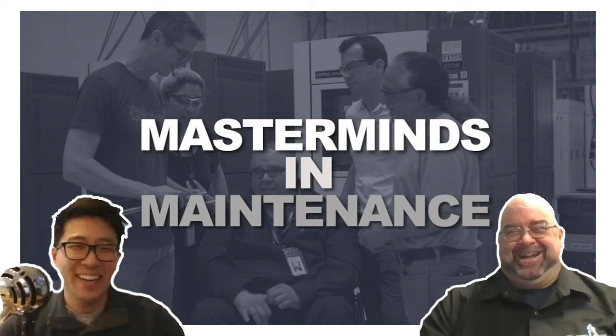Vibration in the wind industry is determined to be about 56% accurate. Electrical signature right now has been determined to be greater than 90%. Wow. Now, what is the primary difference and why is that? Electrical signature is a system analysis. There are things we will detect much later than vibration or ultrasound and other things, but we will see them. And there are things we'll see that they will never see, but we're going to see it all at once.